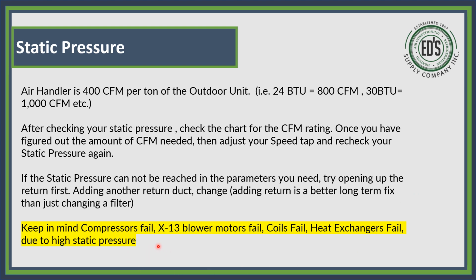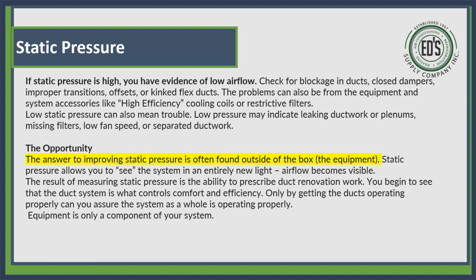Keep in mind compressors fail, X13 blower motors fail, coils fail, heat exchangers fail, all due to high static pressure. If static pressure is too high, you have evidence of an airflow issue. Check for blockage in your ductwork. Maybe the damper's closed. Maybe your flex is kinked. Maybe it's a transition or an offset that's not done properly. Things that you can fix. Maybe you need to change a ductwork fitting. You need to change this.